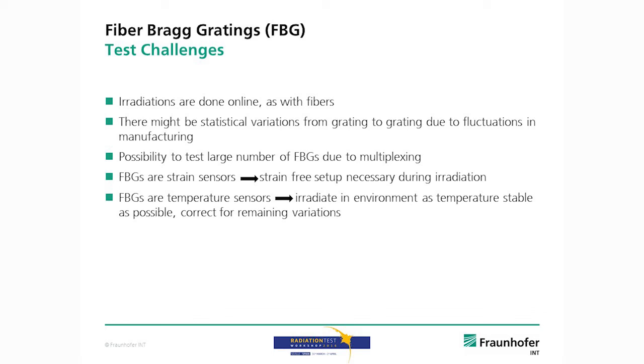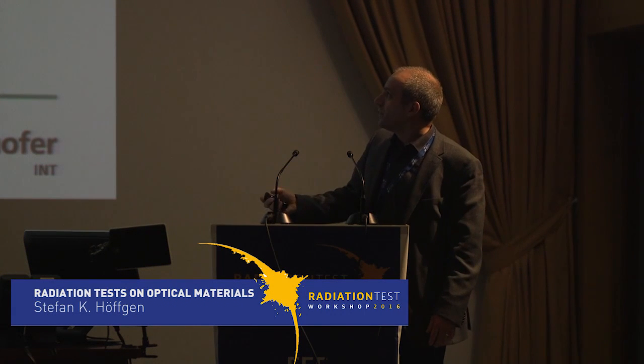And since they are temperature sensors, you have to be very careful to have them in a temperature stable environment during the irradiation, and correct for the small changes you always have. If you put the irradiation source in the room, you always will change the temperature a little bit because you introduce an energy source. Thank you.